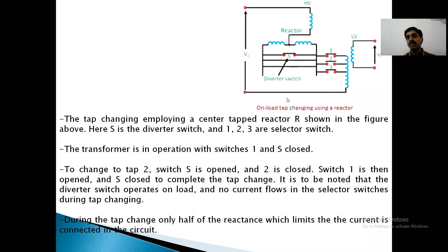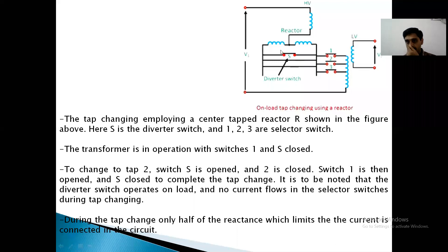Here is one example of an onload tap changing transformer — a high voltage winding with reactor midpoint tapping. These are the different taps connected to the winding. The total high voltage winding has taps, and we have one diverter switch. Let us see how it operates.